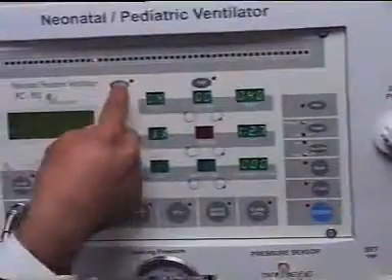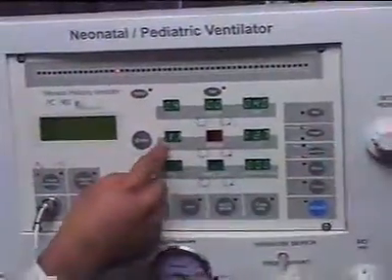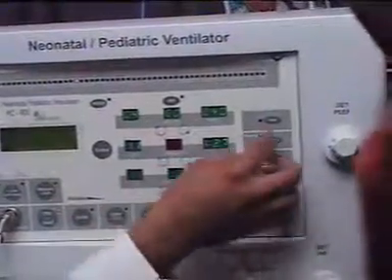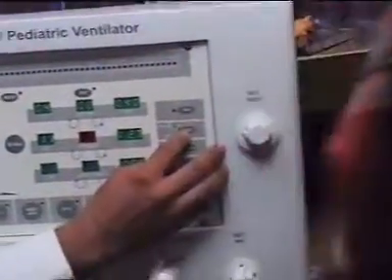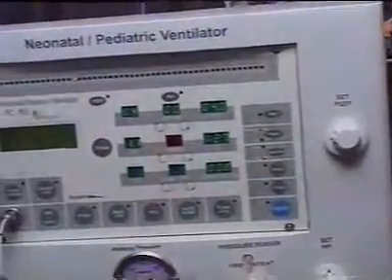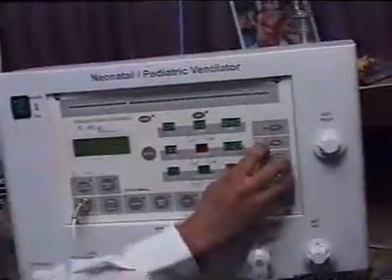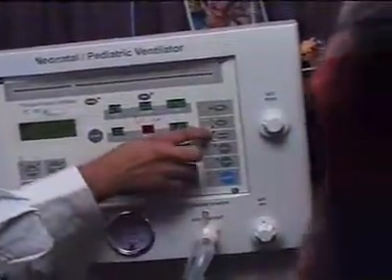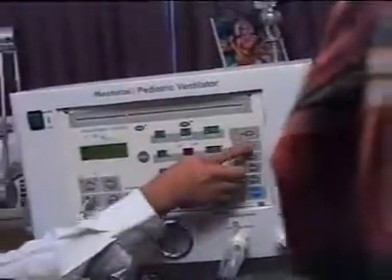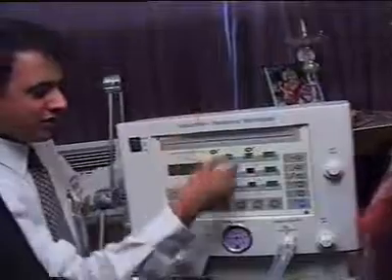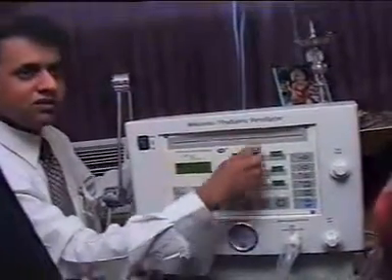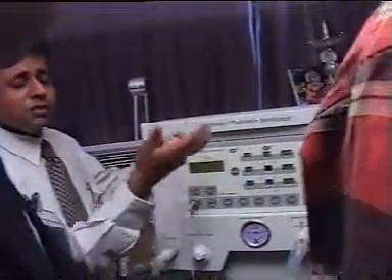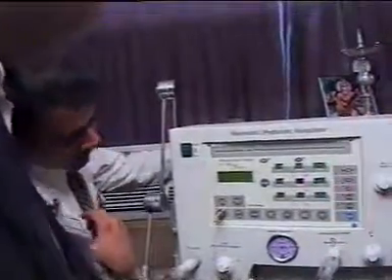Now, this is what you had said. You have the PEEP, you have expiratory time, inspiratory time, inspired volume. This is the tidal volume which is given, and this is something which is important. This is the trigger device, which is also known as the sensor. This trigger you can set to pressure or flow. Remember I told you pressure drop, flow drop, or volume drop. The best of them for newborns is the flow drop rather than pressure. Whenever the baby gives a trigger to the ventilator, you will get a trigger indicator here, or you can set it to -2, -3, -4, -5, whatever you want, depending on how much effort you want the baby to make to trigger the ventilator.